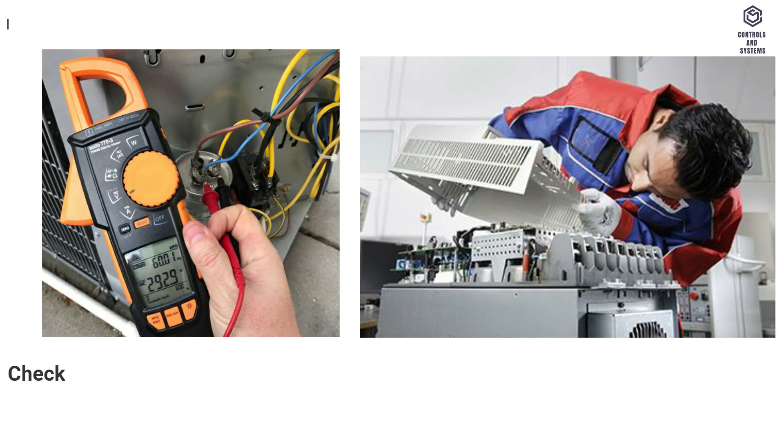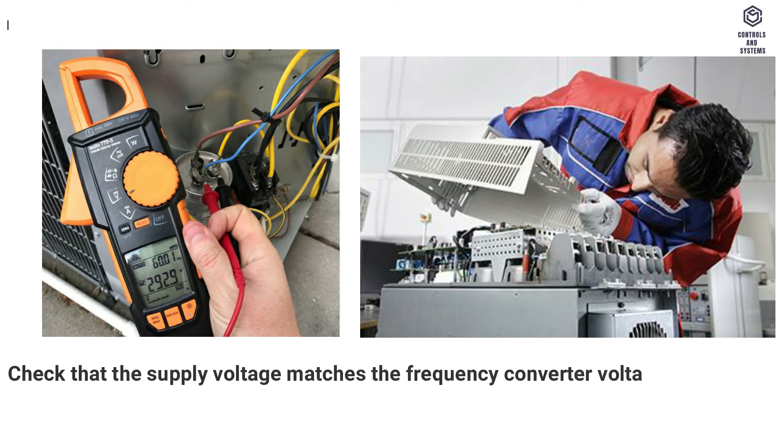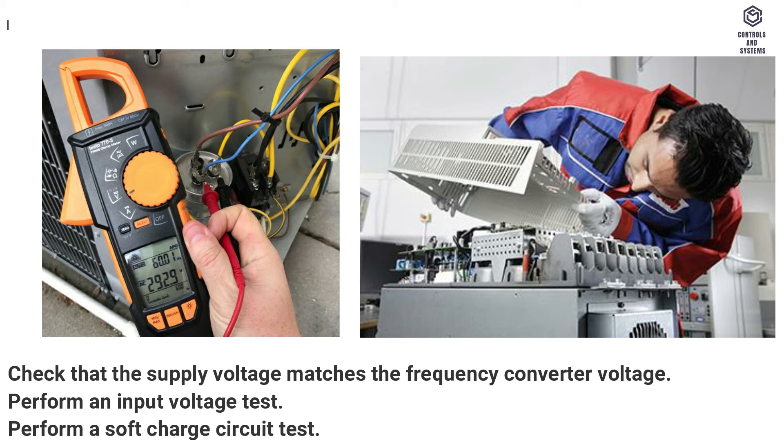Troubleshooting methods: Check that the supply voltage matches the frequency converter voltage. Perform an input voltage test. Perform a soft charge circuit test.